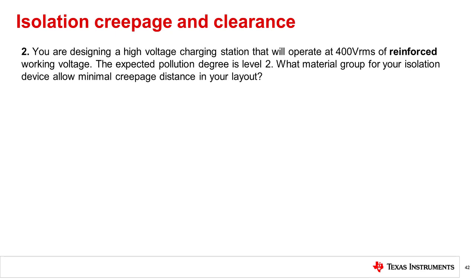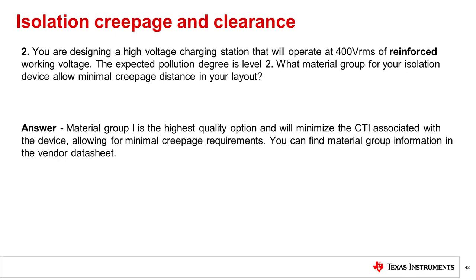You are designing a high-voltage charging station that will operate at 400 volts RMS of reinforced working voltage. The expected pollution degree is level 2. What material group for your isolation device will allow minimal creepage distance in your layout? Material group 1 is the highest quality option and will minimize CTI associated with the device, allowing for minimal creepage requirements. You can find material group information in the vendor datasheet.